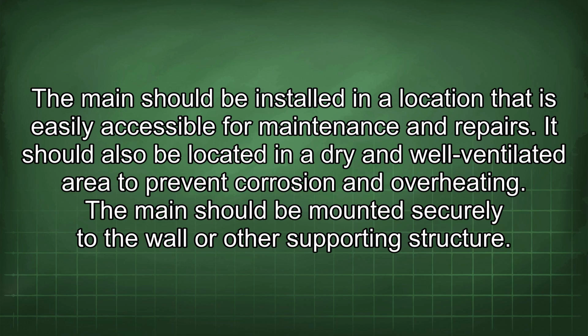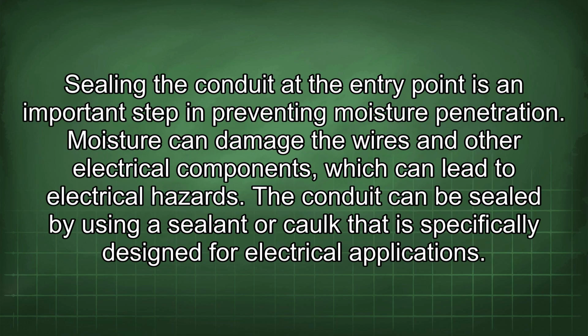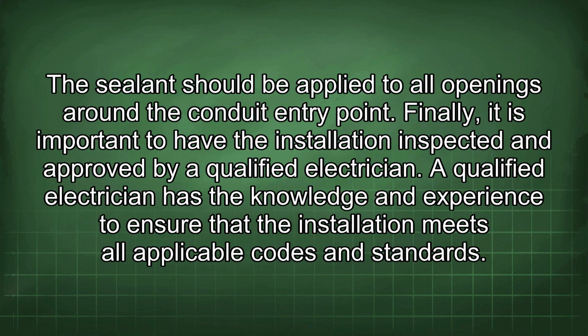The main should be mounted securely to the wall or other supporting structure. Sealing the conduit at the entry point is an important step in preventing moisture penetration. Moisture can damage the wires and other electrical components, which can lead to electrical hazards. The conduit can be sealed by using a sealant or caulk that is specifically designed for electrical applications. The sealant should be applied to all openings around the conduit entry point.